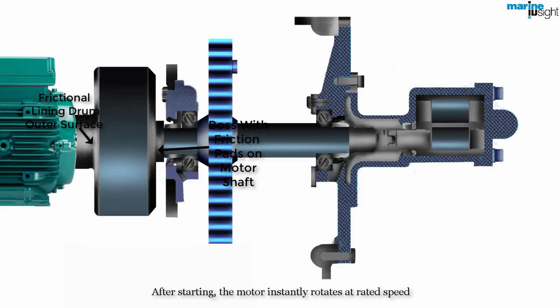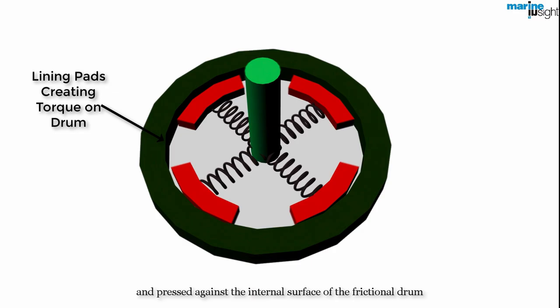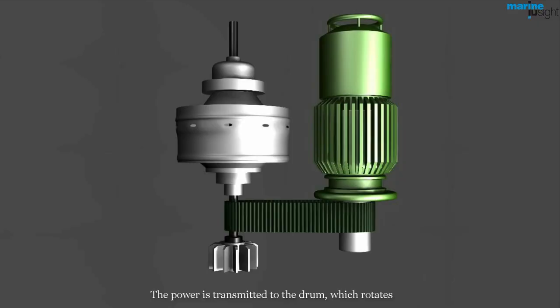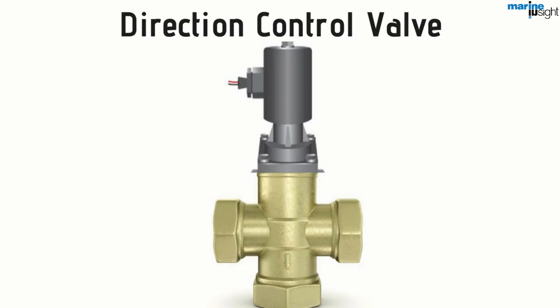After starting, the motor instantly rotates at its rated speed. The centrifugal force makes the frictional lining pads go outwards and pressed against the internal surface of the frictional drum. The power is transmitted to the drum, which rotates the separator bowl as the drum and lining pads slip together. The bowl would typically attain its full speed in 2 to 5 minutes, depending upon the make of the centrifuge separator.